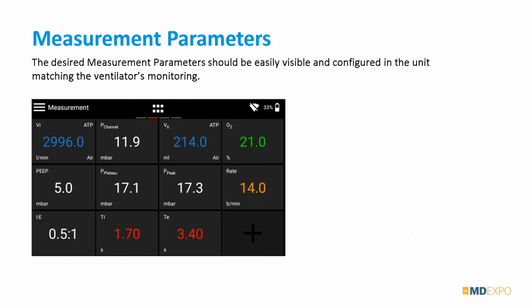Okay. The last thing on the settings side, as Kerwin already mentioned, there are a lot of different parameters that gas flow analyzers can measure. So typically about 25 or more, depending on the brand or make you're using. And one other important point is that we make sure that we take a look at the right parameters. Sometimes, for example, ventilator manufacturers call something like peak, that's the peak pressure during the inspiration phase, and another ventilator manufacturer calls that PIP, for example. Or as Kerwin mentioned, rate, frequency, stuff like that, right? So they can have the same thing named differently.